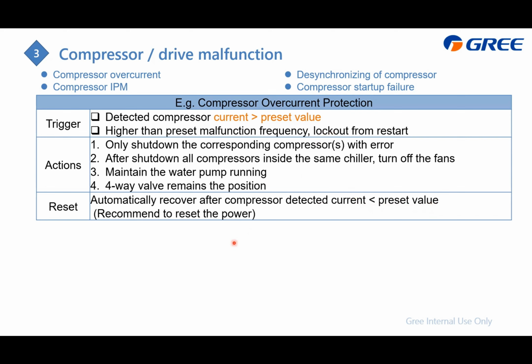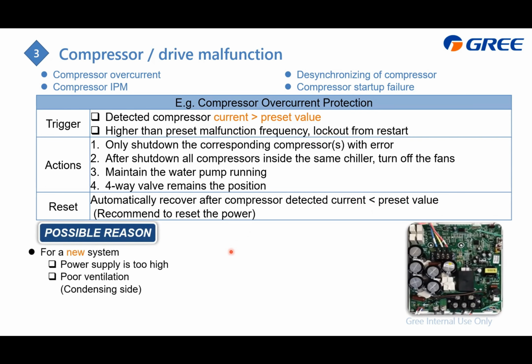And here is how to do the troubleshooting for a completely new system. This time you just need to check whether the power supply, especially the voltage, is too high or not. And next, check whether the ventilation is not that good. Maybe something is wrong, or some foreign objects block the ventilation, just consider the condensing side.